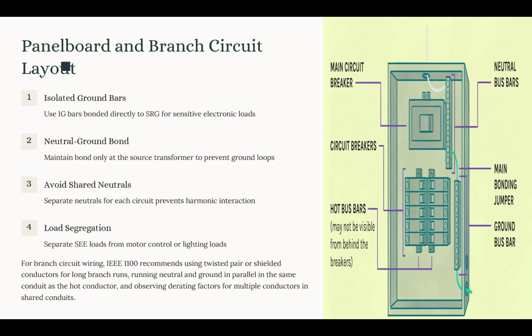If we have a poor panelboard or branch circuit layout, this could end up as one of the most common causes of logic malfunction, communication errors, and intermittent resets in those sensitive devices. The recommendation for that has several aspects when we talk about the recommendation of the IEEE 1100. One is the isolated ground bars, which are dedicated ground bars connected directly to the signal reference grid, independent of other equipment grounding conductors.